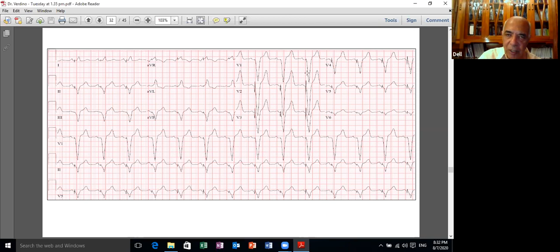Now, how do you evaluate a pacemaker? Five steps. One step is missing from this slide. The first question you ask is: is the pacemaker pacing? You know that by finding a spike. If you don't find a spike, you put the magnet. If the spike appears, then this means that there is electromagnetic interference or there is crosstalk.